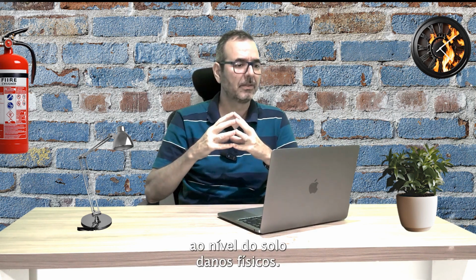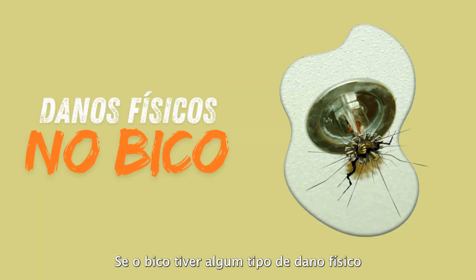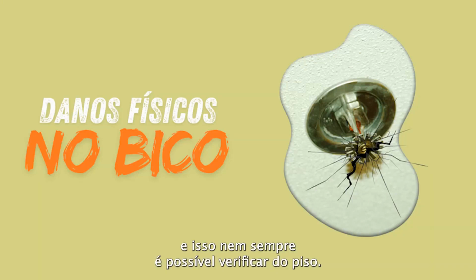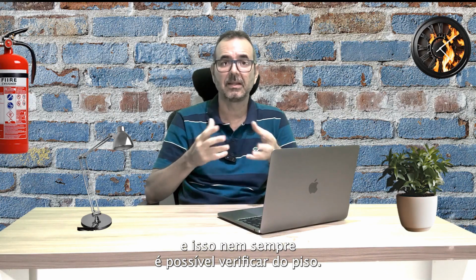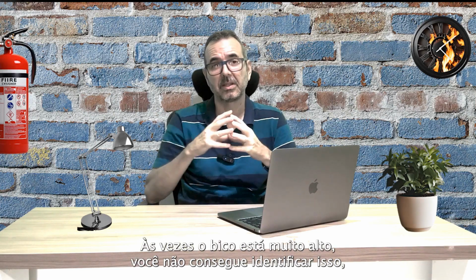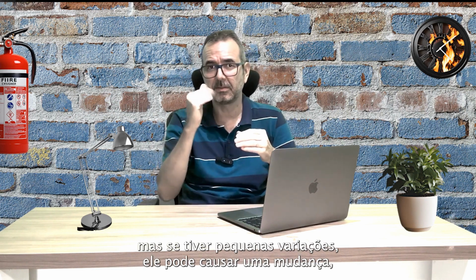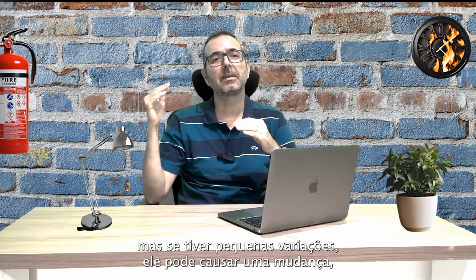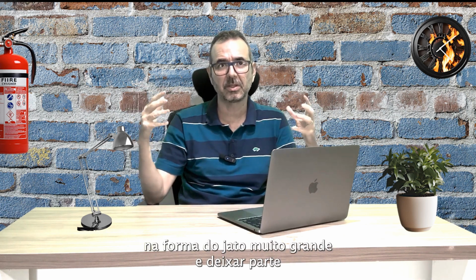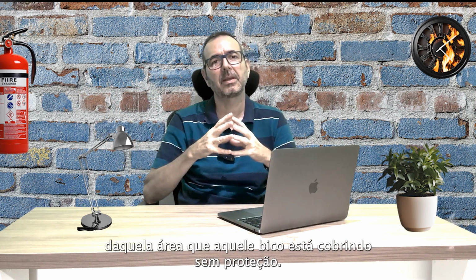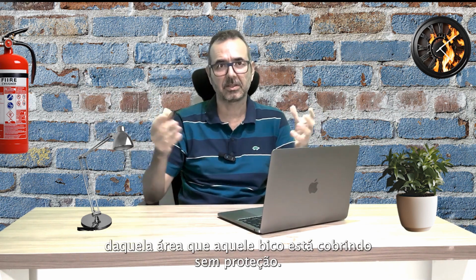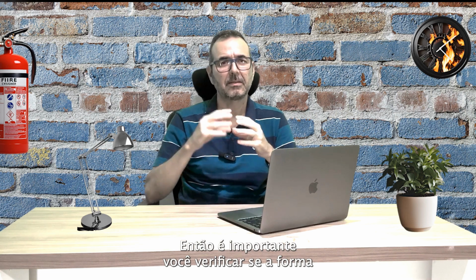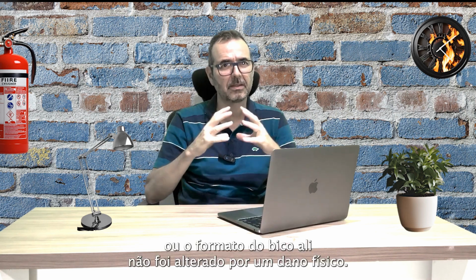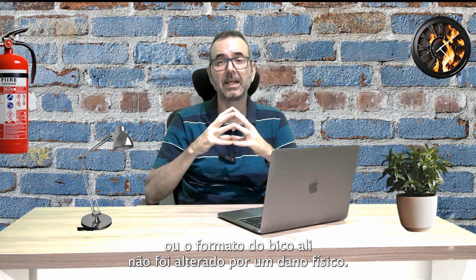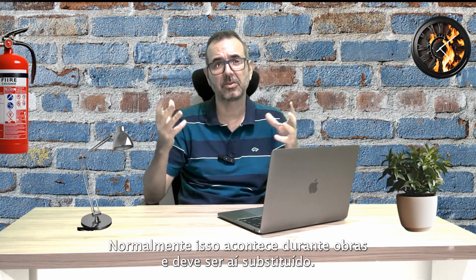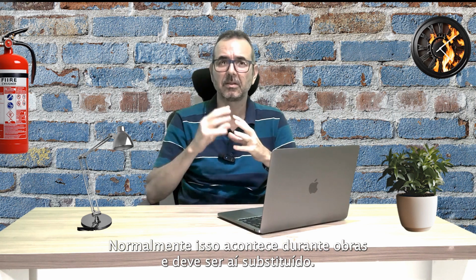Physical damage. If the nozzle has any type of physical damage, it is not always possible to verify this from the floor. Sometimes the nozzle is too high to identify it. However, even small variations can cause a significant change in the shape of the spray and leave parts of the area that the nozzle is covering unprotected. So it is important for you to check if the shape of the nozzle has not been altered by any physical damage. This usually happens during construction, and this nozzle should also be replaced.